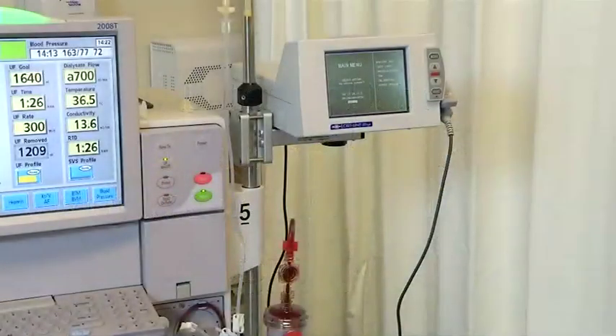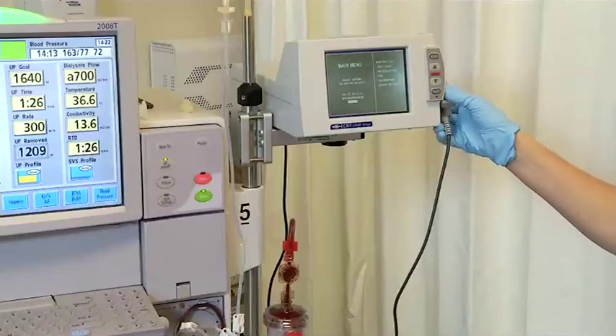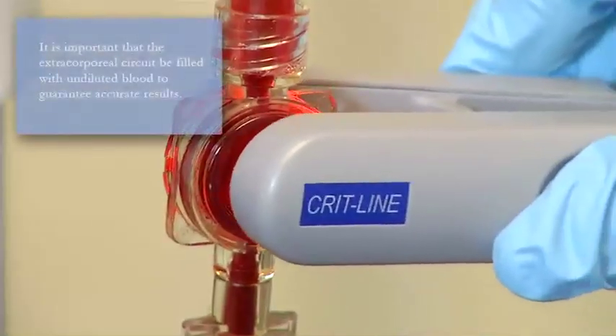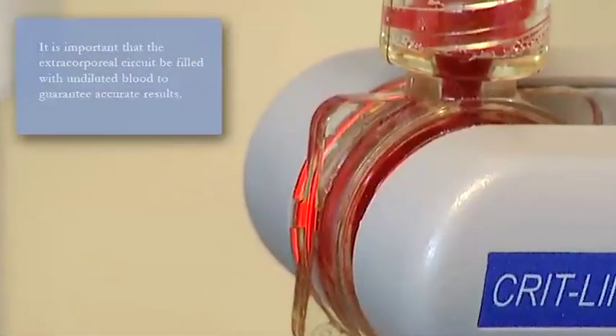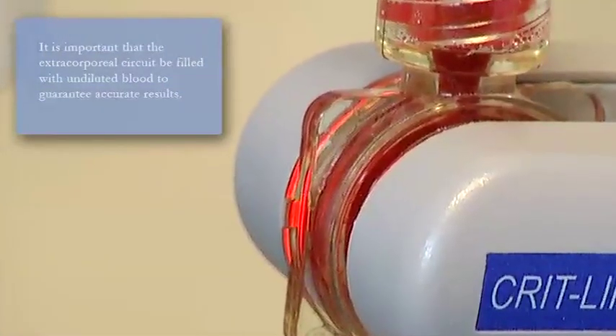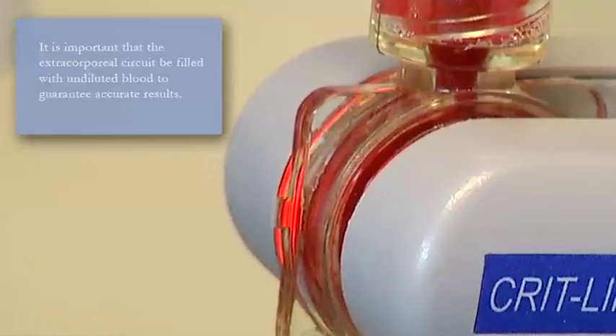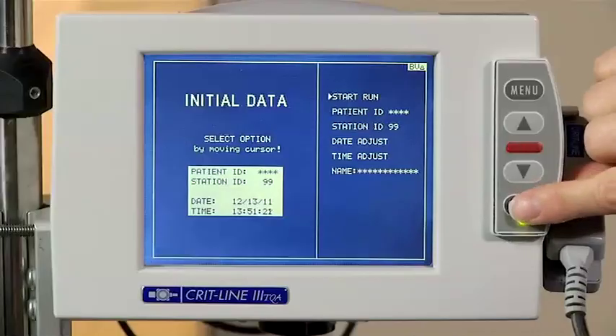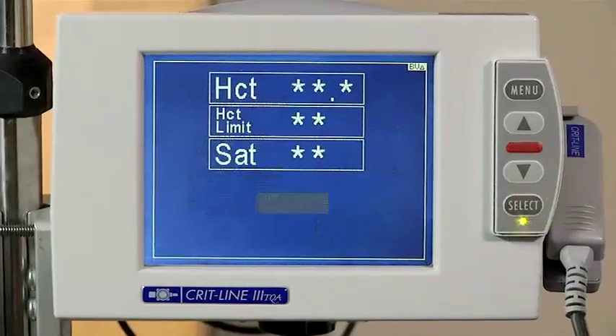Three to 5 minutes after starting the dialysis treatment, and when no air or saline is present, place the sensor clip so that it is perpendicular to the blood chamber. The sensor clip will glow red when the monitor is turned on. Choose Start Run and press the Select button. The CritLine monitor will display the startup screen.